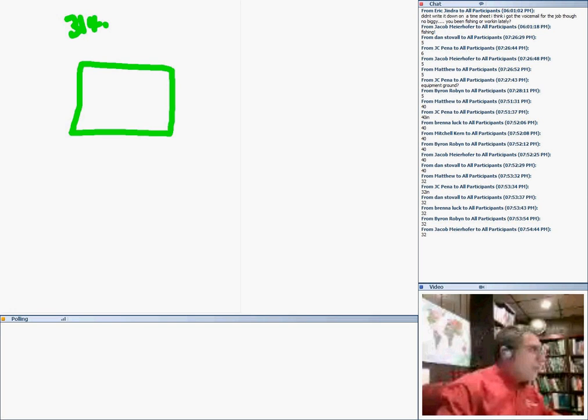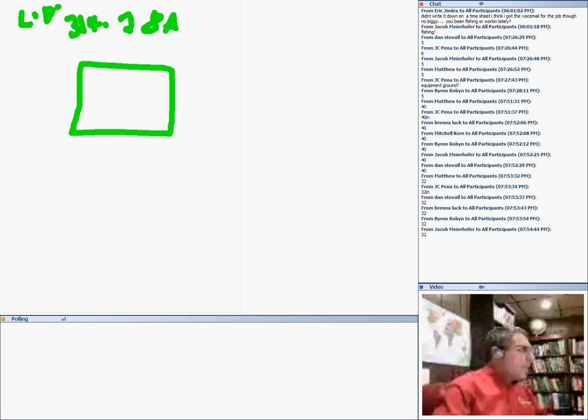Sizes. They have a couple of ways of sizing handholes, guys. Handholes and handhole enclosures shall be sized in accordance with 314.28. So we're doing handholes, and a handhole is right in the ground. So using it for low voltage, guys, you're going to treat it as a pull box. You're going to apply the rules of 314.28. There are the rules of a pull box. This is for low voltage, meaning voltage 600 or less.